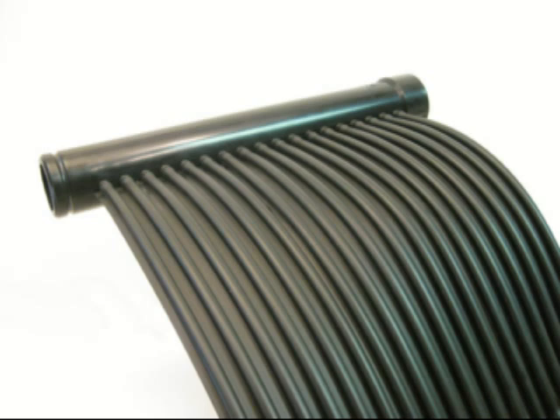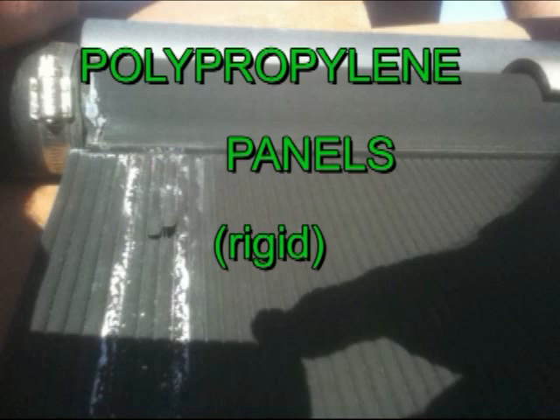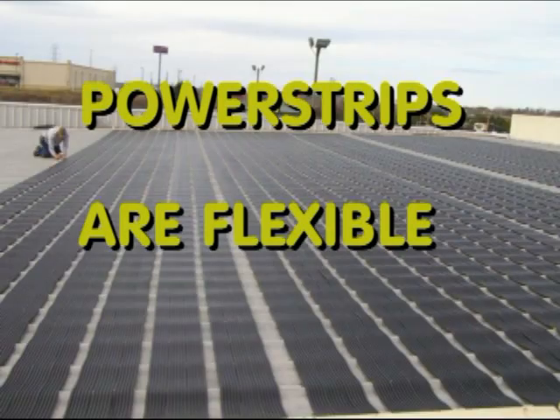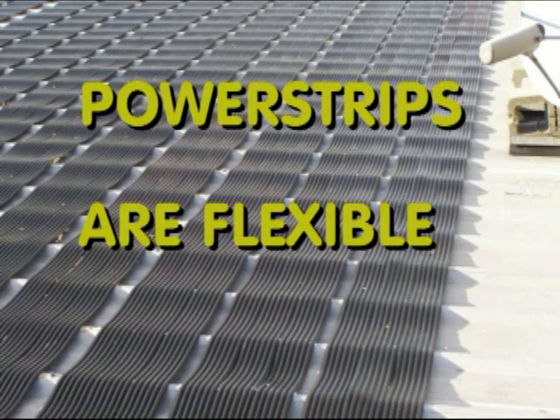You'd never do a flat roof system like this with a regular rigid polypropylene collector. They have to be on a slope — you have to get all of the water out. It only takes 3 degrees C or 37-38 degrees Fahrenheit air temperature for water to freeze in a black surface radiating heat out to the night sky. So rigid collector types are very vulnerable to freeze damage, and it freezes everywhere — it even froze in Miami recently.